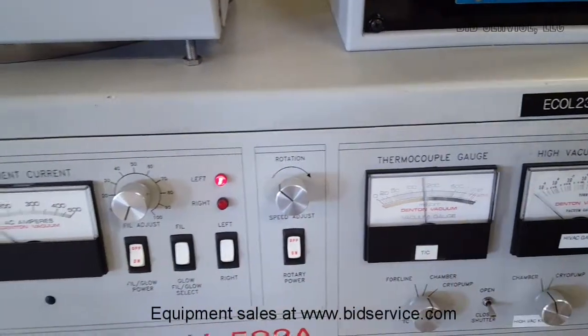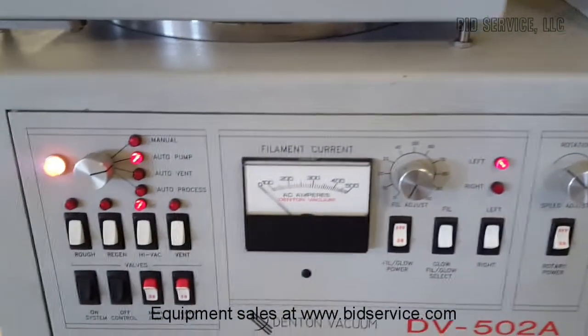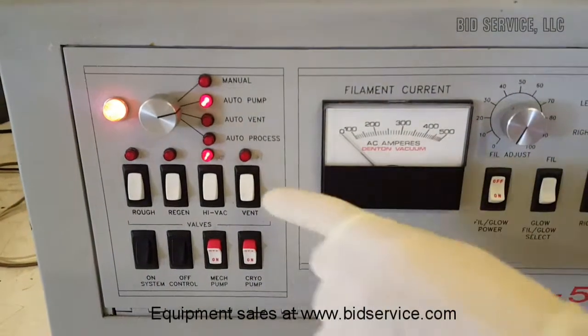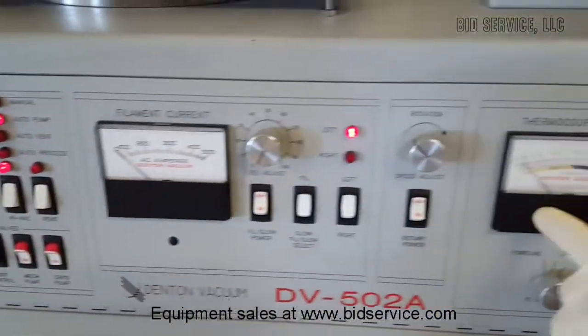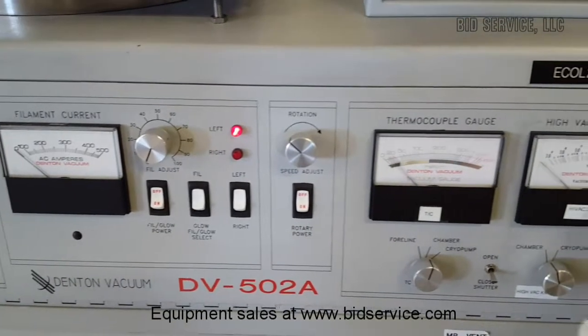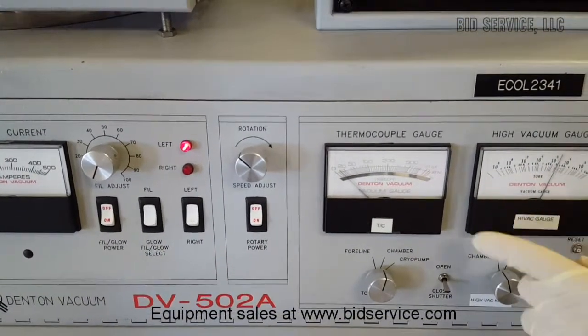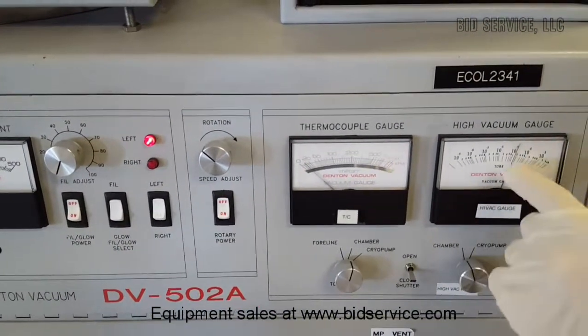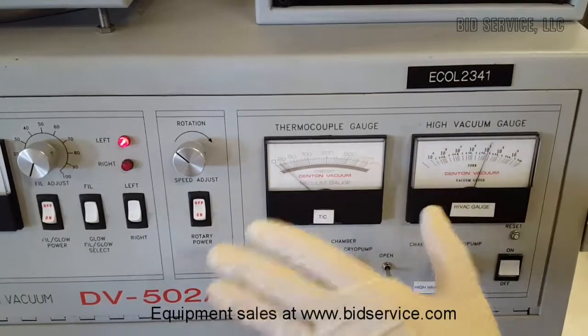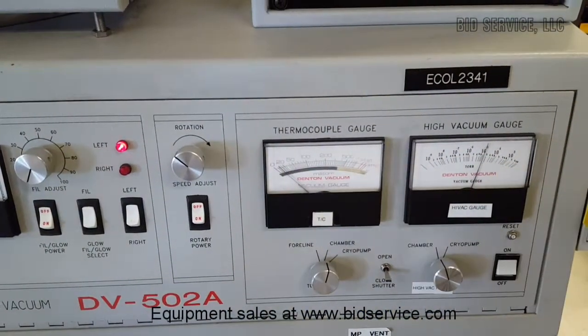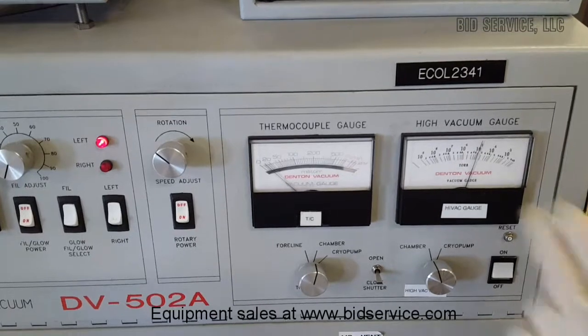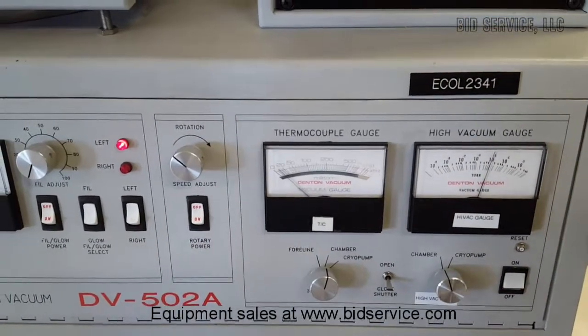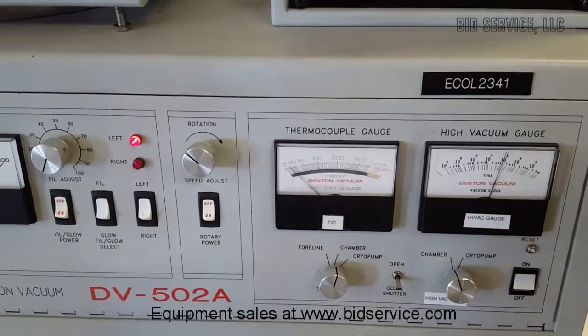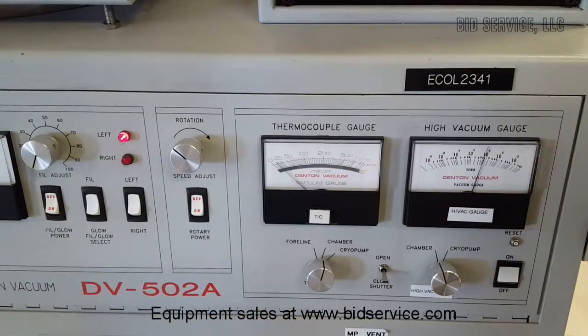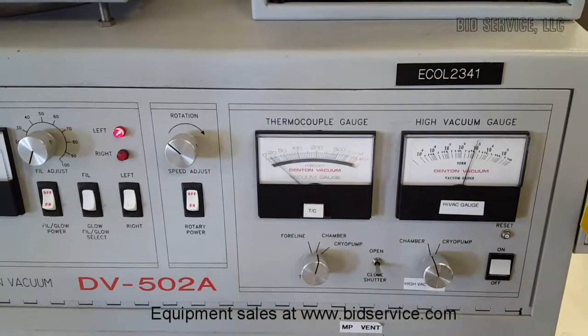the high vac valve is going to open. High vac valve open. You see that the pressure dropped quickly, and then in about 15 seconds they'll turn on the chamber gauge. So you can see after having it open and turn it on, it's already in the 1 times 10 to the -5 going into the 10 to the -6 range, and it'll sit here under high vac in auto pump mode, and it just stops there, becomes idle under high vac.